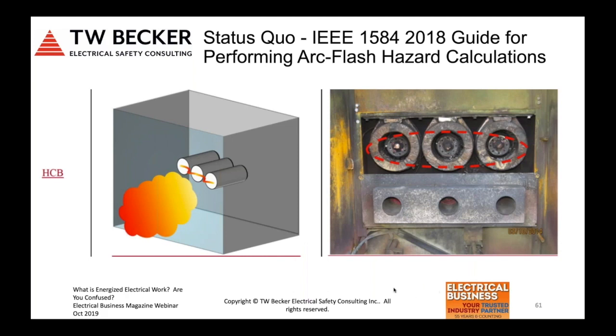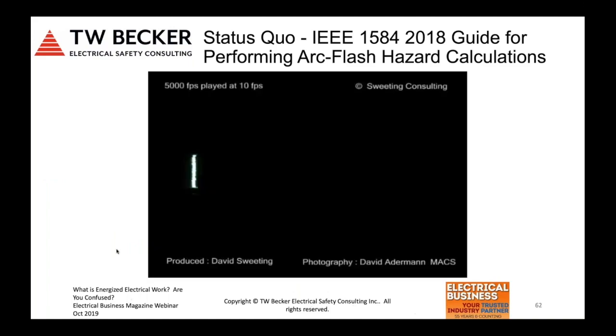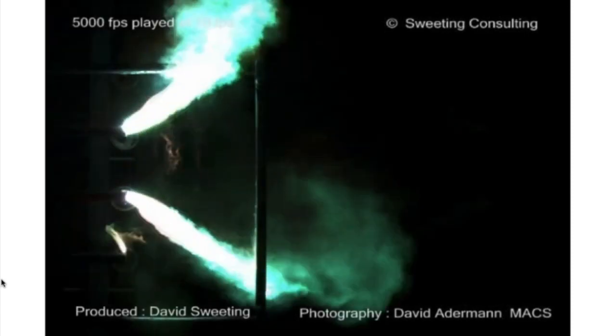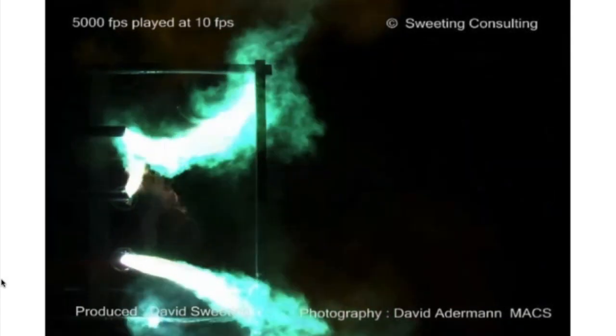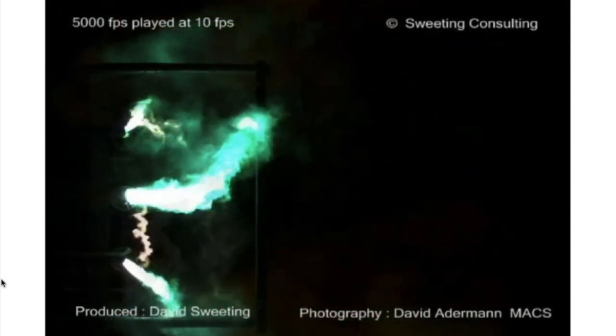What you see here is the ends or the tips of the electrodes. And again, what happens is it's an ejected arc that now comes out, and the incident energy will be directly at the worker. So the incident energy will be a higher value than the vertical conductor in a box or the vertical conductor box barrier box electrode configuration. All right, so I'm going to try and see if I can get this to run. There we go. So you're going to see ejected arcs. So this is ejected arc, 5,000 frames per second. It's like 3 hoses with high pressure water that are turned on. So remember, this is very fast. This is occurring. This is what our eyes can't see. So what we see is the incident energy will be directed more at the worker in front than being reflected out of the box with the vertical conductor box or vertical conductor box barrier box electrode configuration.